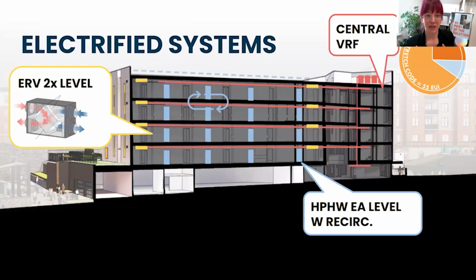And this was kind of the happy medium of equipment scale because it allows the maintenance to be done from the corridor side, so you don't have to interrupt tenants, versus having an ERV in every residential unit. Then you have a lot more coordination for the maintenance. But it does offer a little bit more redundancy, the way unit by unit ERVs would, by having it on every floor, by having 2 in each location. You get to do some maintenance and you can shut down pieces of the system without the entire building having to go offline for maintenance. Whereas if you had a centralized rooftop system, you wouldn't have as much flexibility. So it kind of was that happy medium.